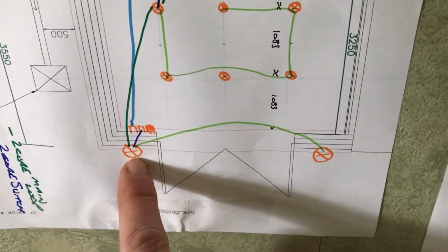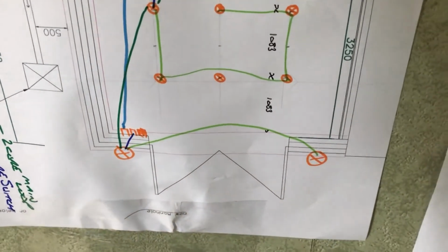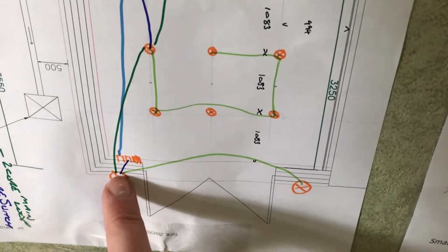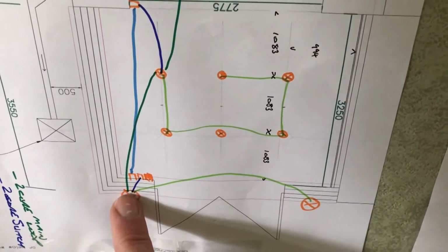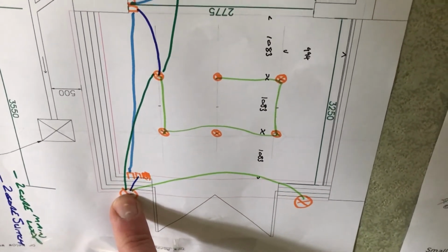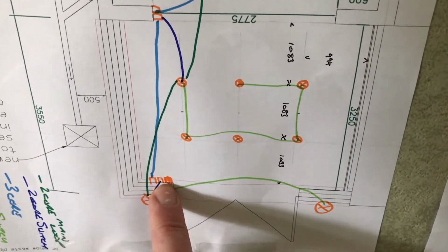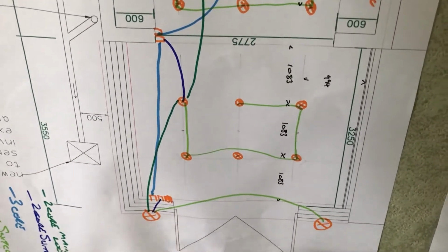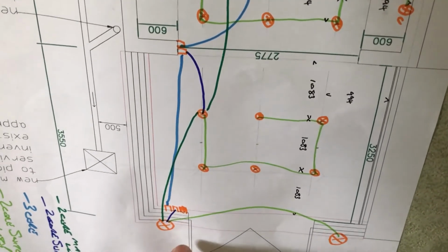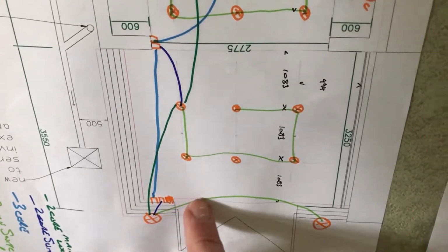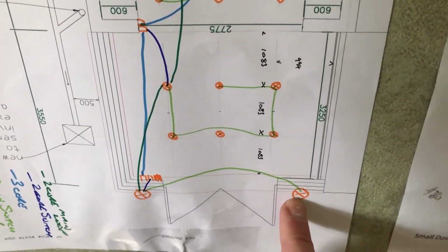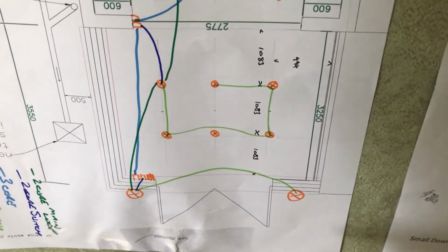Now these ones will be on a switch because you don't want it on a sensor, because you've sat on the patio, you don't want them turning on and off as they do and don't detect you. So the main power comes into the first light, we switch down, we only need a single way switch here because you're going outside, so you're either in or out. And then just a little switch loop to the second lamp on the other side of the patio door when it goes in.